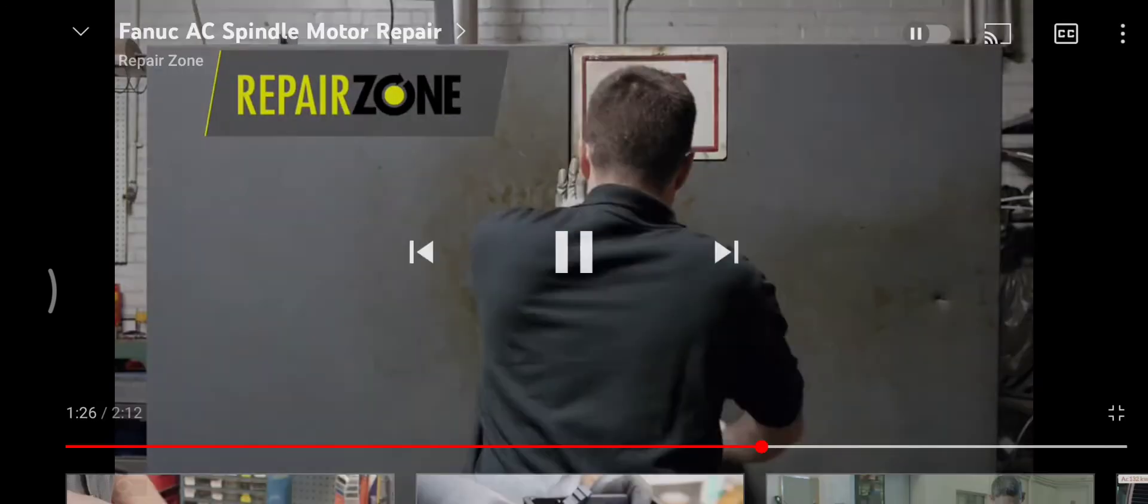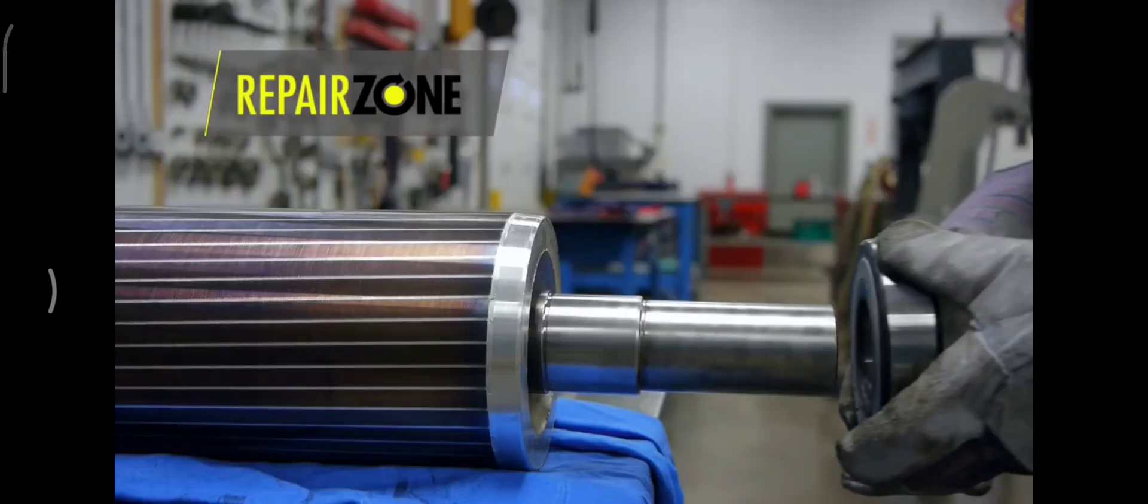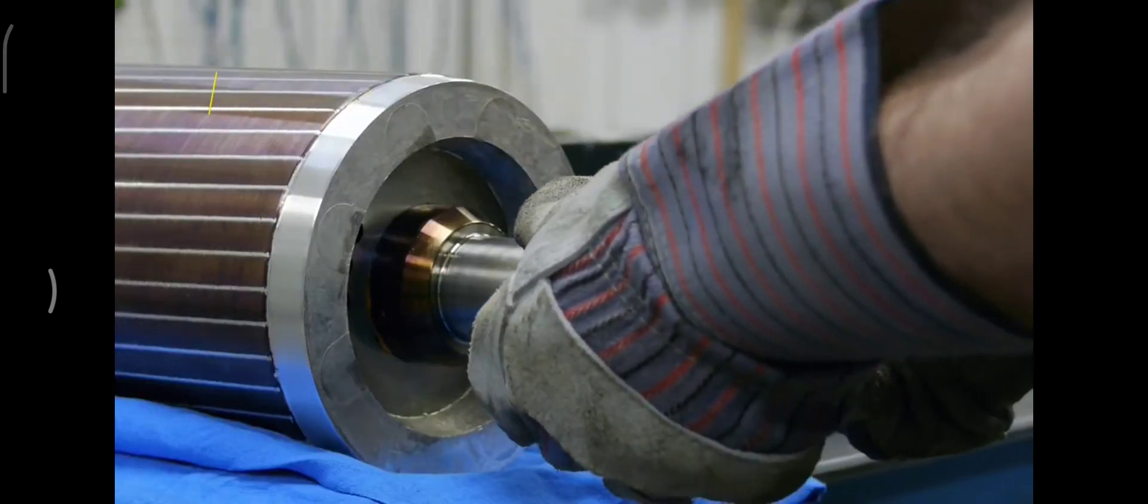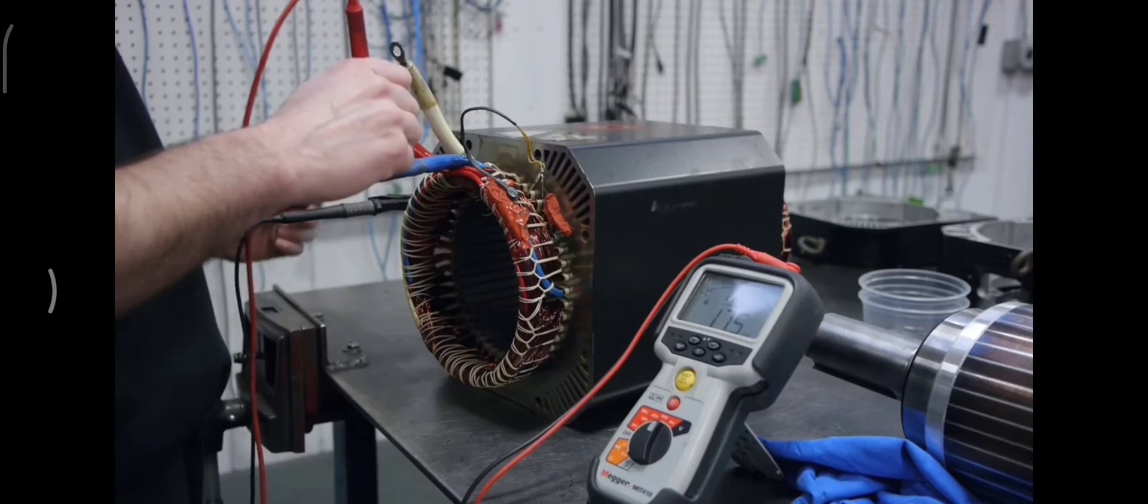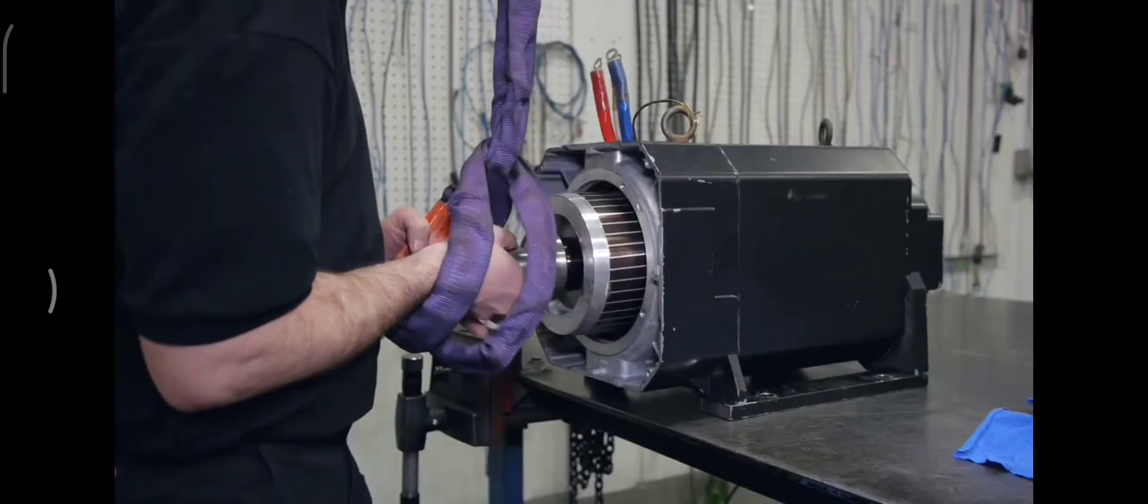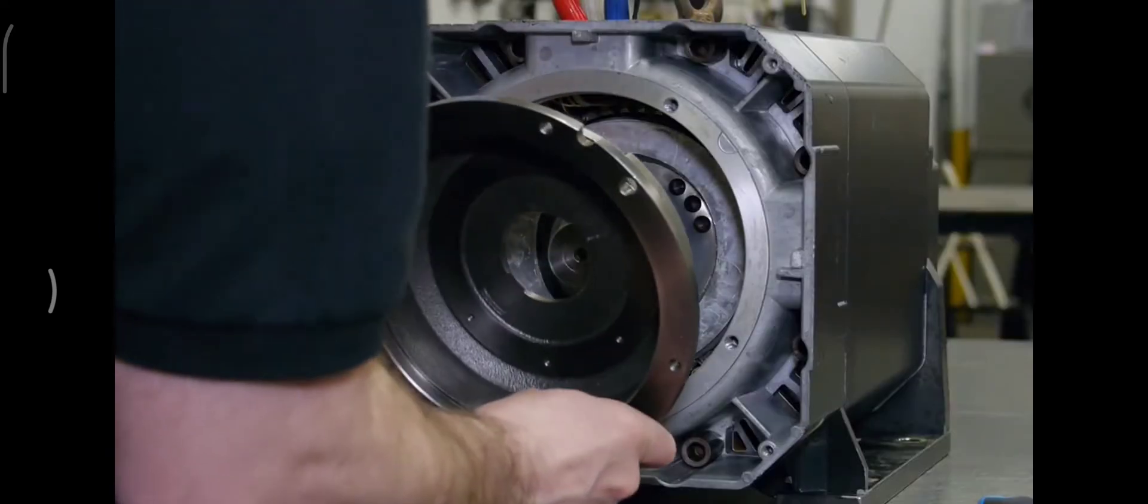It is then baked overnight in our oven. During assembly, new bearings are installed. The stator is megged again after the wash and bake. The rotor is put into place. Motor housing and end bell are installed.